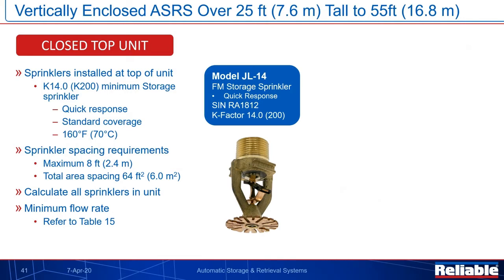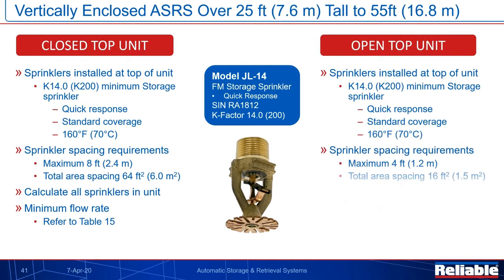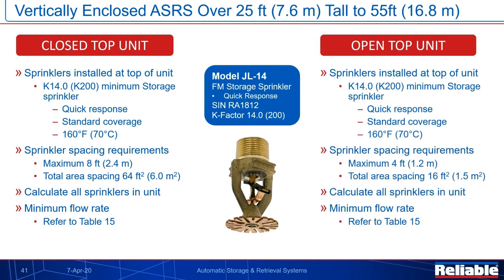And just like before, we have the open top unit requirements as well. Again, forcing us to use a minimum of K14 when we exceed 25 feet. And our spacing has again been reduced down to 4 foot.